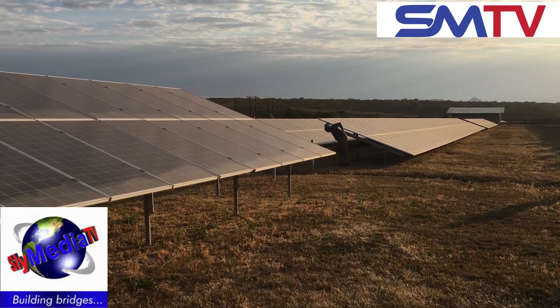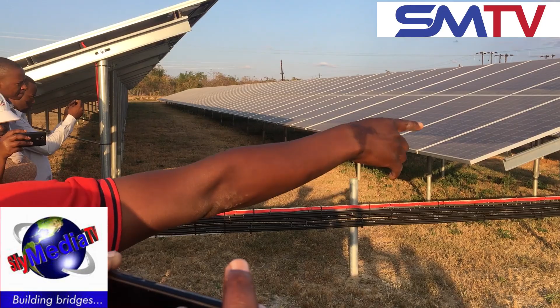So you can see on this block, those are the combiner boxes. From here to the far end, it's 120 panels, which is 6 strings. Then this one is 6 strings again. Then they are combined in that box. So you can count all those boxes. Then this is 95 square aluminum cable, coated. This is now carrying 1000 volts from the combiner box, in positive and negative, to the control room.